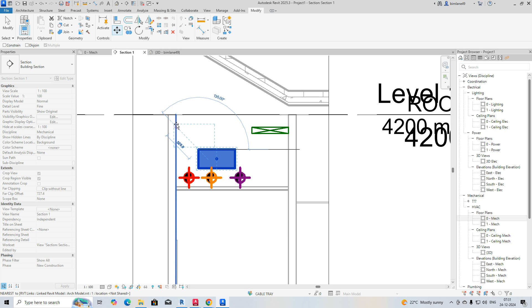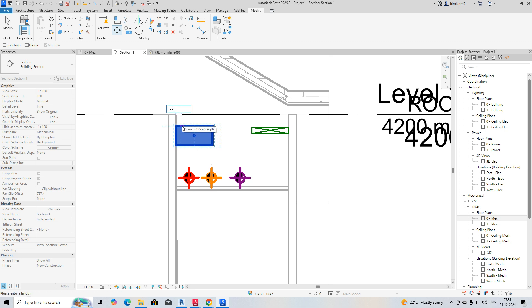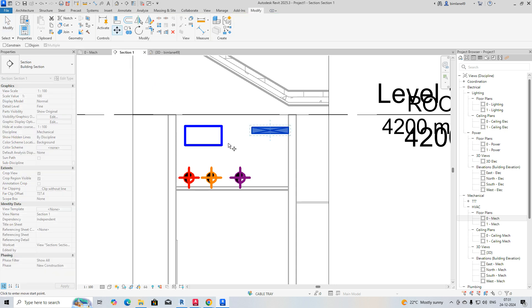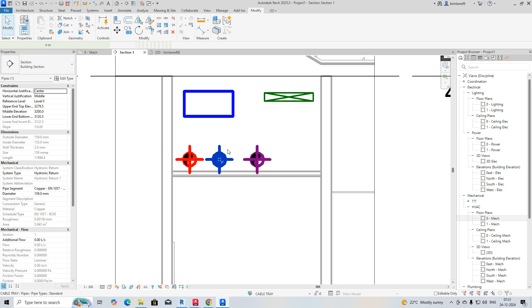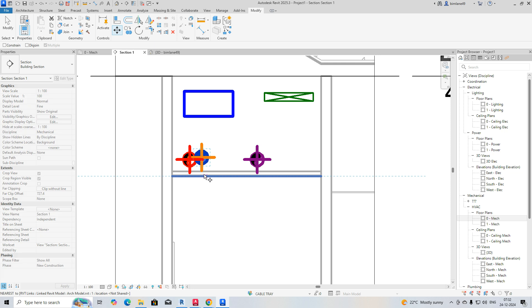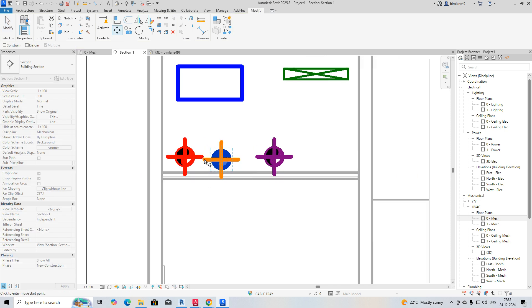Just 200mm down, put it there. And this duct we can put on the right side above, just giving some distance from the wall — 150mm at least. Then it will come like this, and the cable tray also like that — maybe 100mm from the tray. And this pipe distance also we can arrange. From here we can give this pipe to this pipe 150mm gap, and same level we need to put it — just align it.